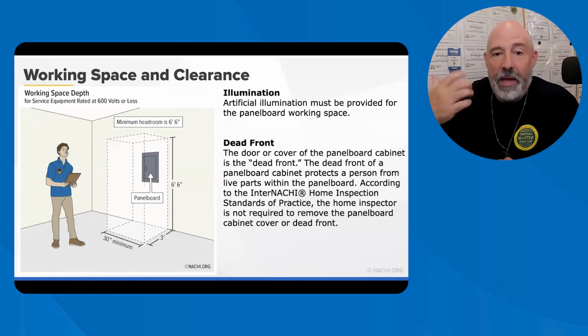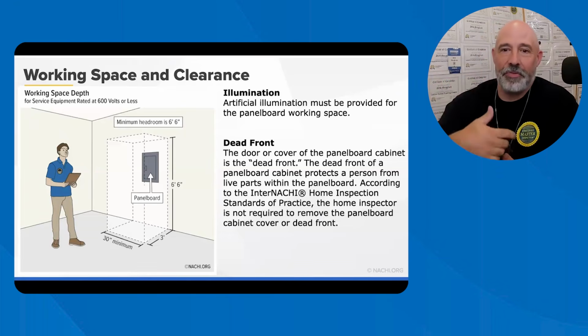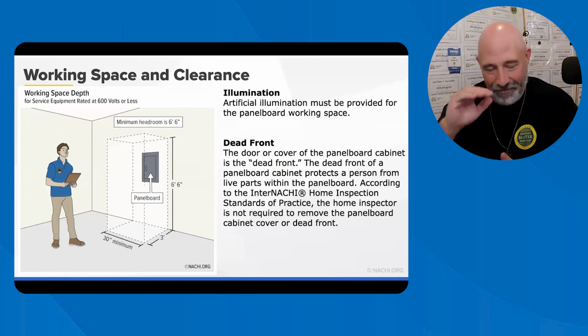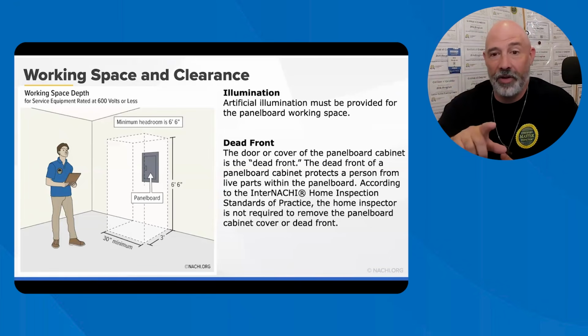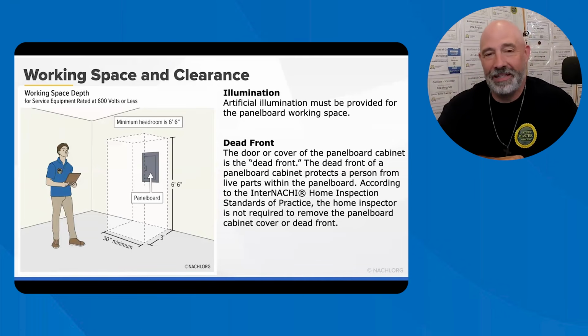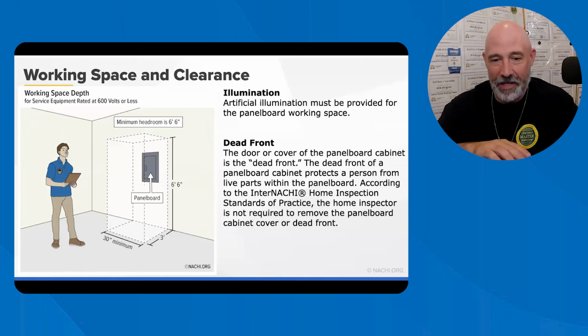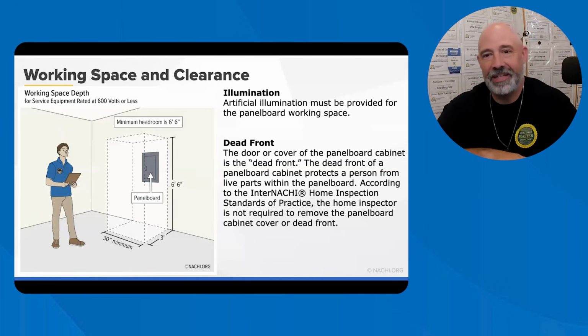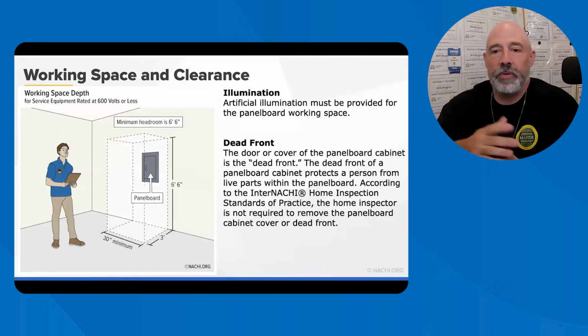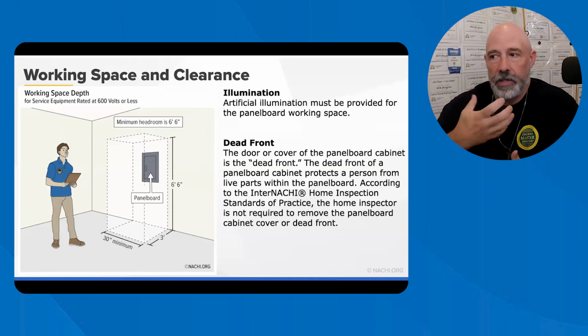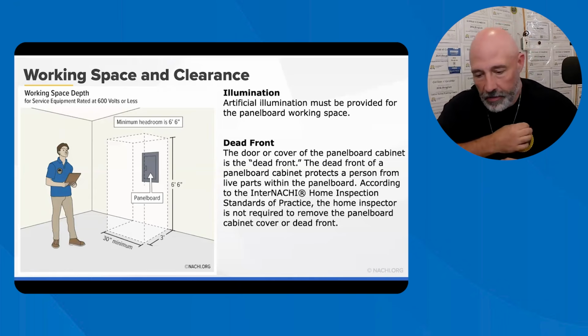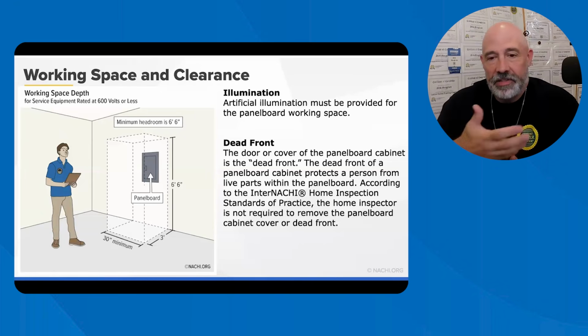Panel boards should not be located in bathrooms. I can't tell you how many times I've seen it. I went to a remodel, and the panel board was in the bathroom, and it passed the city inspection. I said, you're not allowed to have this in the bathroom, right? Oh, I didn't know that. Huh, all right, whatever. You also don't want them in clothes closets. It used to be very common in clothes closets, but because of the fabric and the dust that it creates, it's not a good thing to have. You don't want them in toilet rooms.